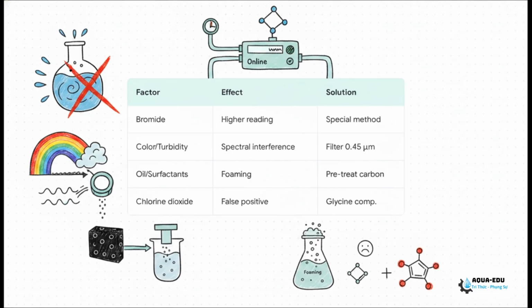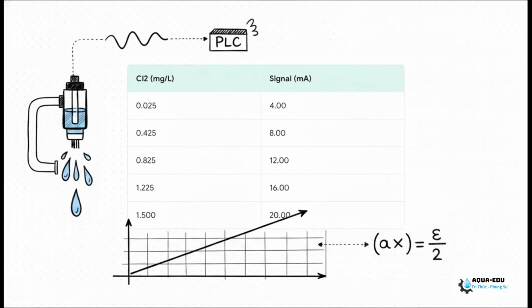Oils and surfactants cause foaming and inhibit the DPD reaction, requiring active carbon pretreatment. And chlorine dioxide? That causes a false positive, requiring glycine compensation. Identifying these interferences is key to reliable data. Check out this exact 4 to 20 milliamp signal mapping. Notice the perfect linear relationship here. 4 milliamps is your baseline at 0.025, and 20 milliamps is your absolute max at 1.5.